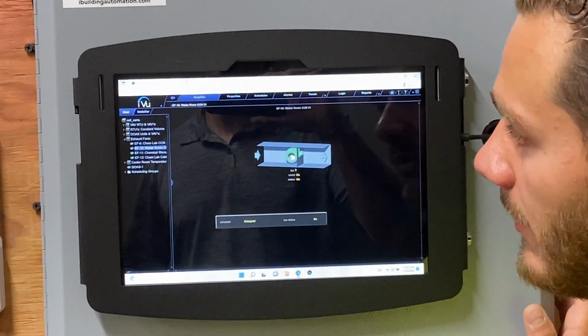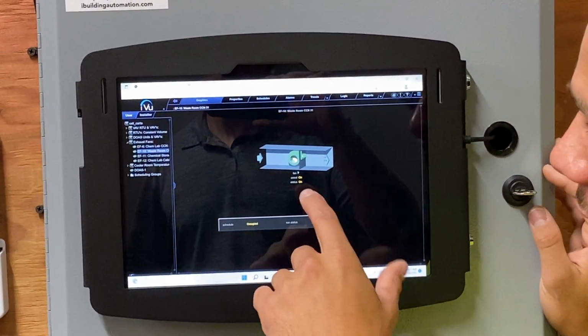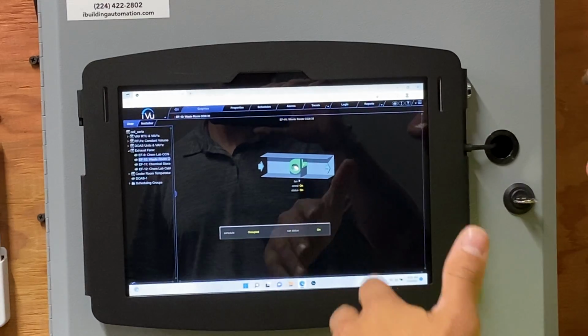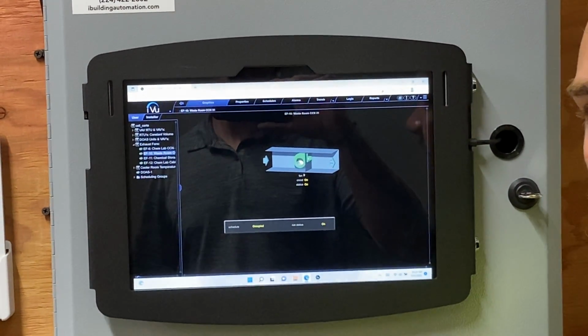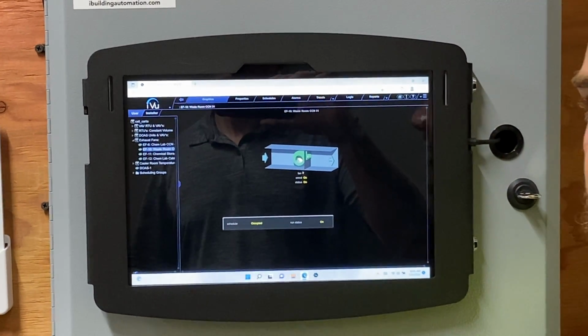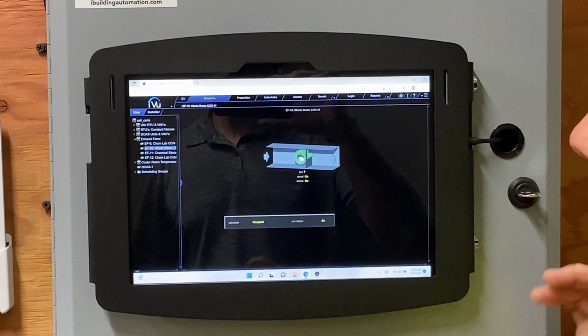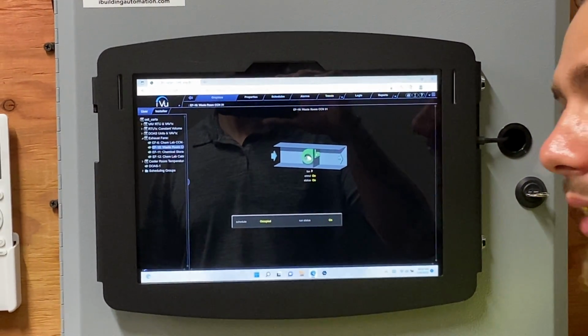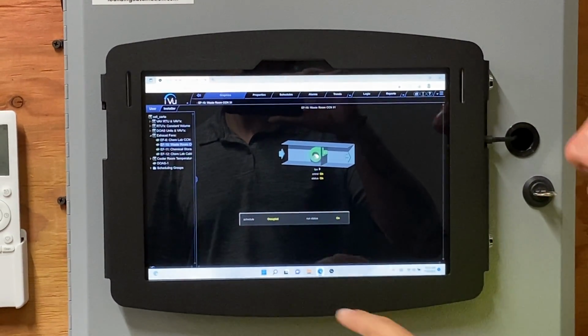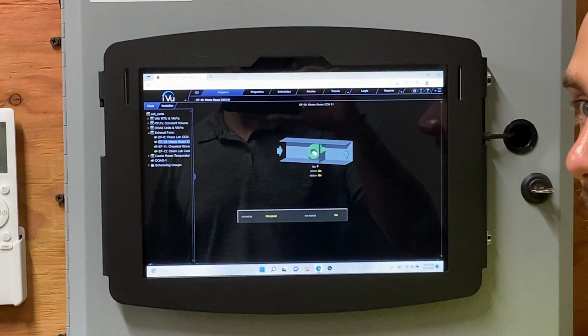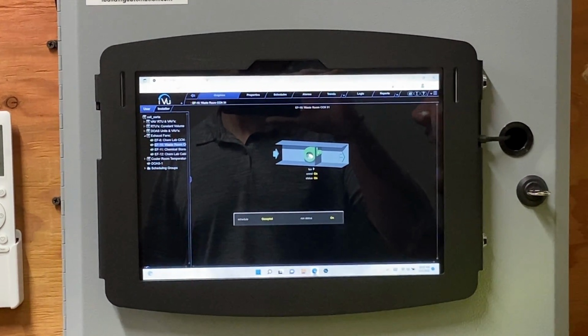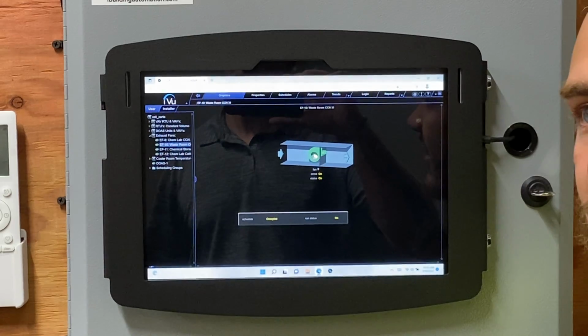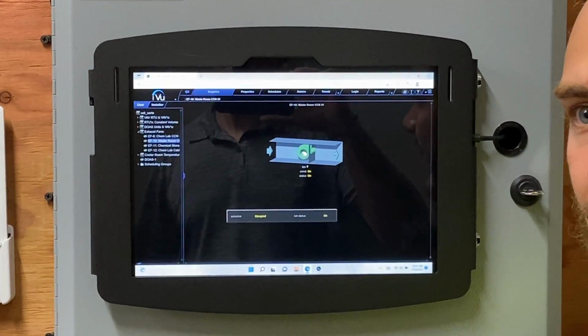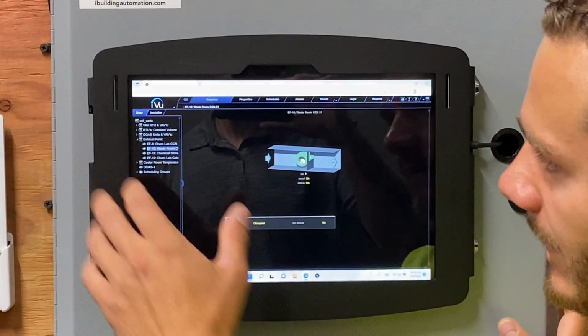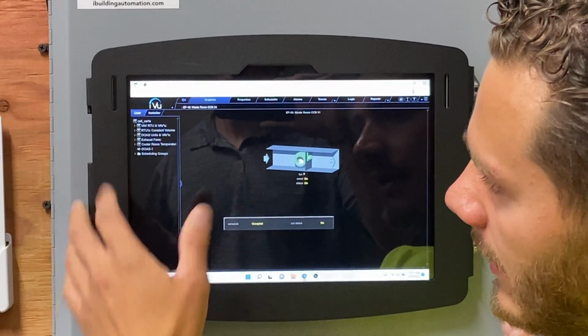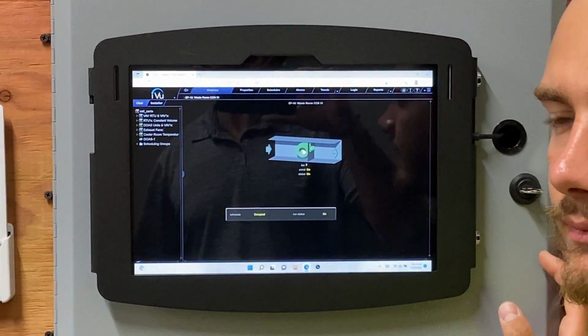As we click in between them all, if for some reason we're commanding this on and the motor locks up, or something terrible happens, and the blade gets out of whack, and we're not actually picking up status, or a breaker was turned off accidentally, it'll say command on, status off. That gives you the heads up that we need to mechanically check what's going on with this piece of equipment.